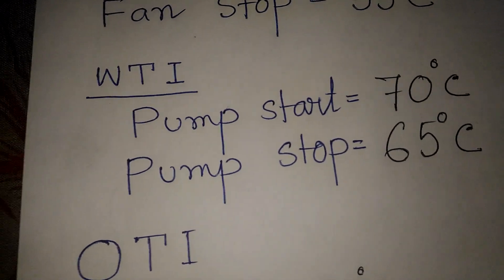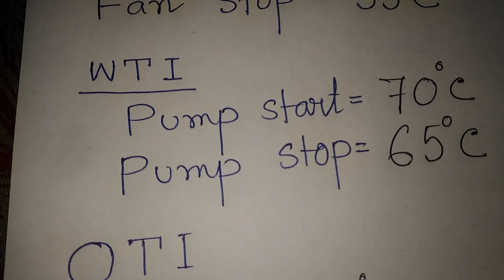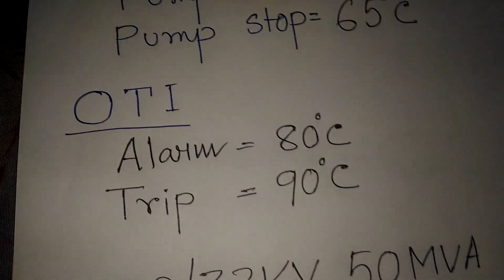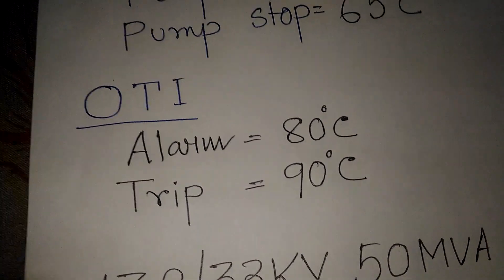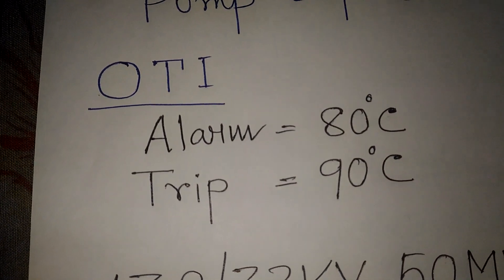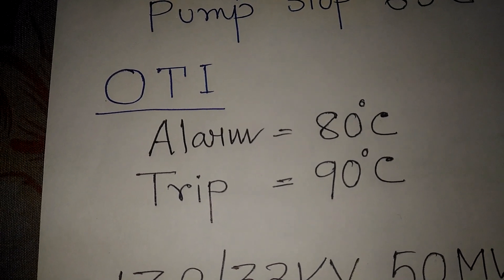And for the pump start and stop, it is accordingly 70 degree Celsius and 65 degree Celsius. And for the OTI alarm, it may be 80 degree Celsius and for trip, it is 90 degree Celsius.